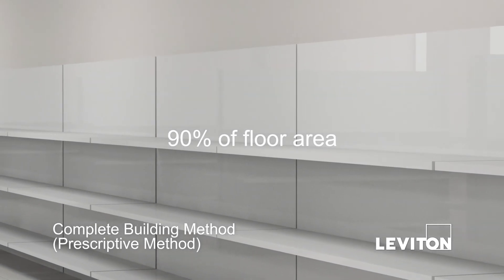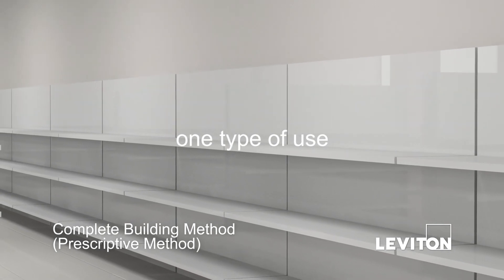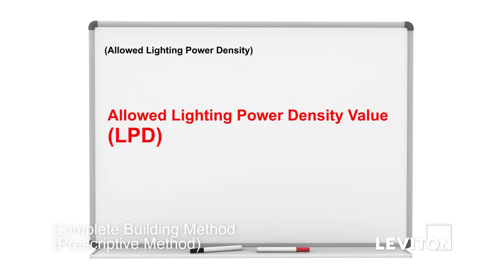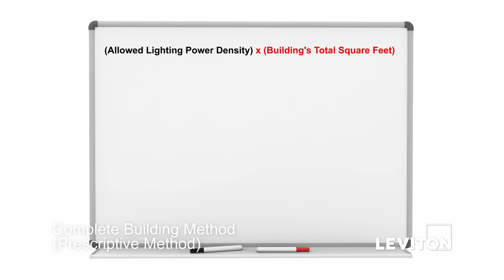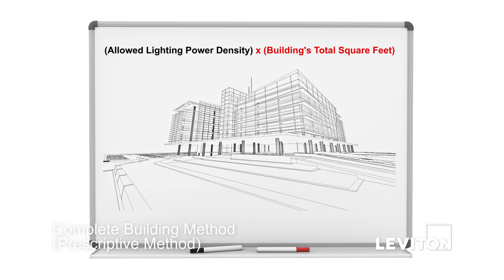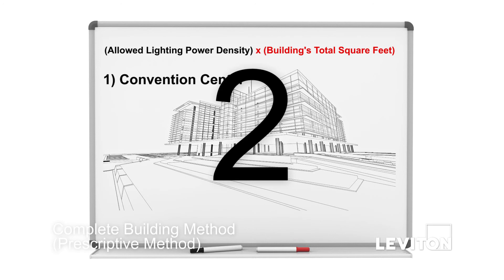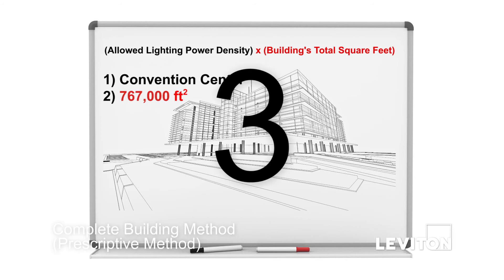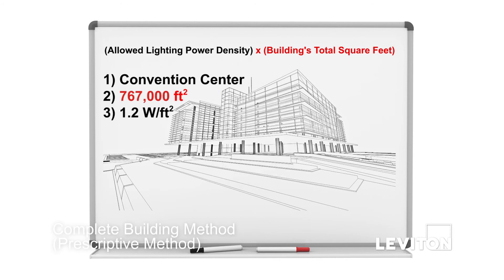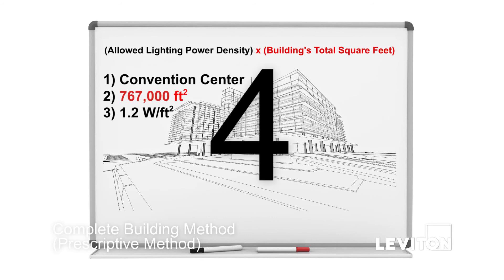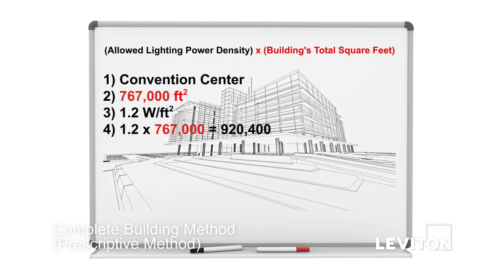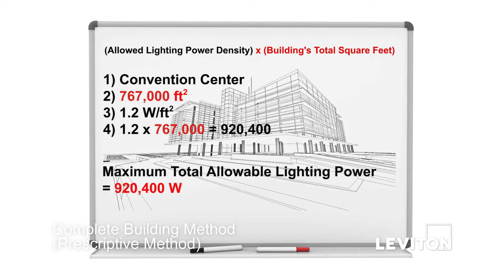Ninety percent of the floor area for the entire building must consist of only one type of use. The complete building method uses an allowed lighting power density value based on building type, which is multiplied by the building's total number of square feet. To illustrate the process: first, identify the building type. Second, identify the total number of square feet. Third, look up the allowed lighting power density value in wattage per square foot for each building type. The allowed lighting power density value can be found in the Non-Residential Compliance Manual. Fourth, multiply the allowed lighting power density value by the building's total number of square feet to determine the maximum total allowable lighting power for that building.